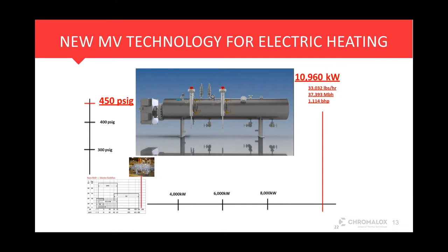Here's a quick look at what one of those systems might look like. I mentioned the 450 PSI—on the large end, that might equate to about an 11 megawatt system with standard pressures and temperatures, around 33,000 pounds per hour of steam. With the electric option, it's scalable in a linear aspect. Since it uses SCR firing, only the power you need is applied, so if larger systems are needed, it's easy to scale up.